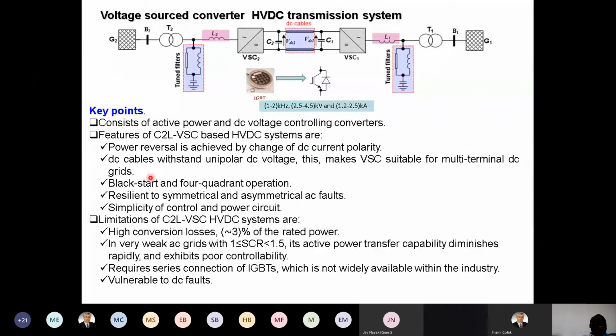The black start, which actually can perform the same function as synchronous machines in case of blackout of a system. If this system is blacked out, you can use this converter to restart the power in this system. And also, 4-quadrant operation, which means actually it can sink and source active and reactive power. So you can transfer power in these directions or this direction, and the same for Q in this direction and in these directions. But remember, the reactive power doesn't go to DC. Only active power can change to DC power. But the reactive power can be circulated within the converter and its AC side. So there is no link, because you can find in some literature, there is no link between this capacitor and reactive power.